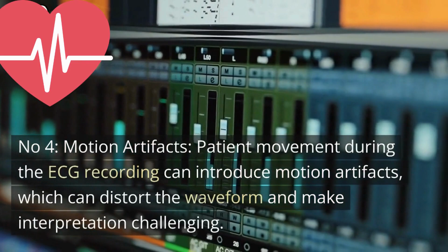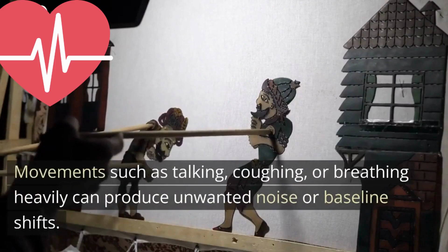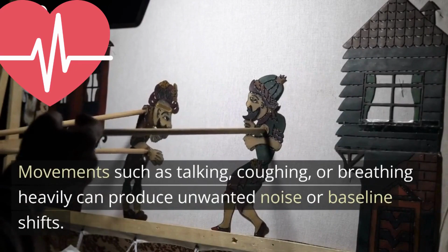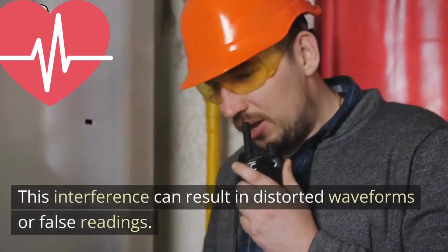Number 4. Motion artifacts. Patient movement during the ECG recording can introduce motion artifacts, which can distort the waveform and make interpretation challenging. Movements such as talking, coughing, or breathing heavily can produce unwanted noise or baseline shifts. Number 5. Electrical interference. Electrical interference from nearby equipment or electrical sources can introduce noise into the ECG signal. This interference can result in distorted waveforms or false readings. Proper grounding and shielding techniques can help minimize this type of interference.